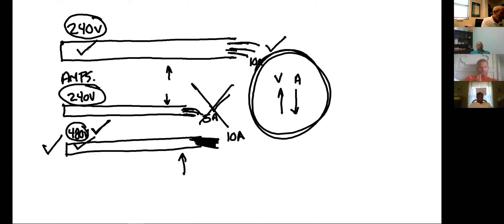240, all right, and I'll put some sizes to it: 2-inch pipe, I'm able to get 10 amps out of it. 480, 1-inch pipe, I'm still able to get 10 amps out of it because I raised my voltage. Voltage raise, amperage drop.